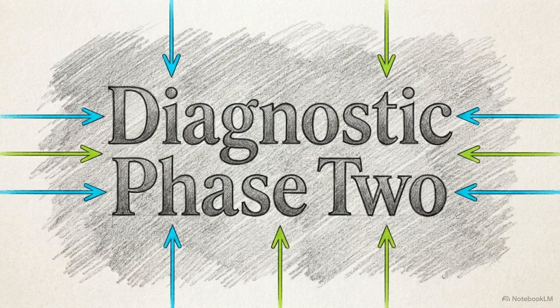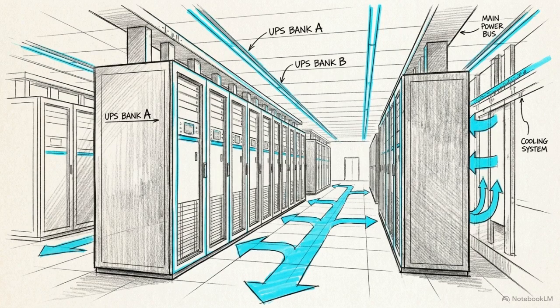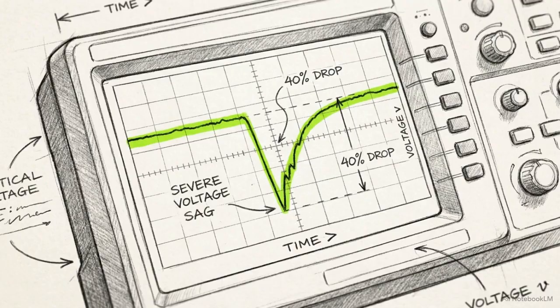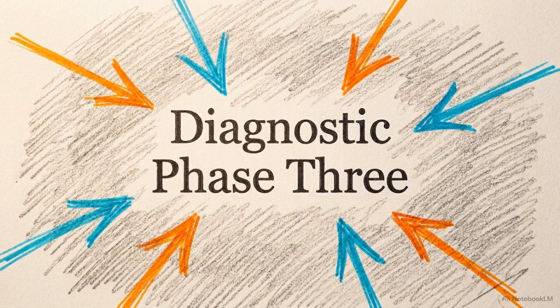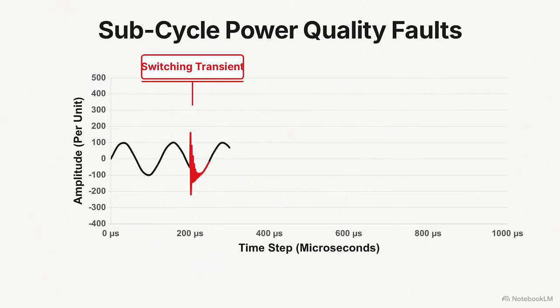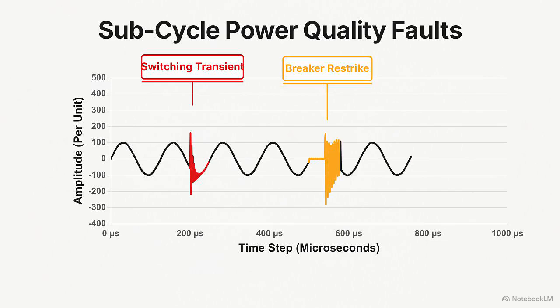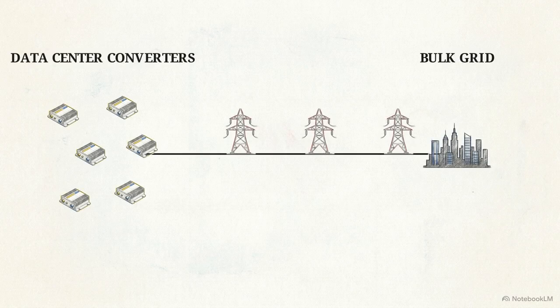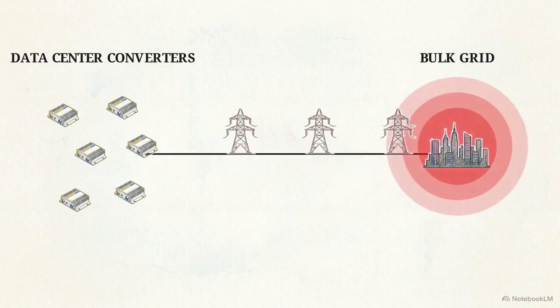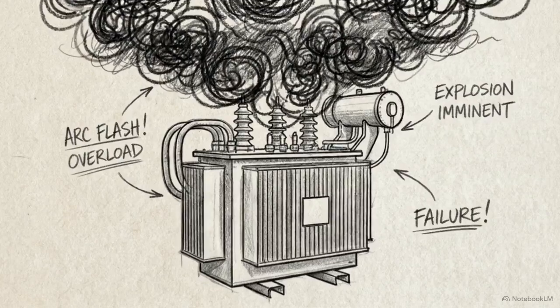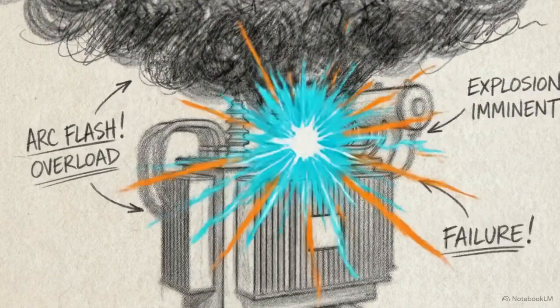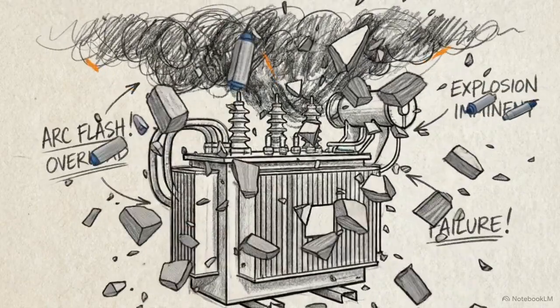The second diagnostic requirement is validating sub-cycle fault ride-through capabilities. The model must capture how the facility's front-end converters and uninterruptible power supply systems respond to severe voltage sags in the span of microseconds. The third requirement is power quality analysis, specifically targeting rapid switching transients, breaker restrikes, and voltage flicker. In weak grid conditions, the control loops of hundreds of individual converters can interact, resulting in hunting behavior that degrades local power quality and propagates through the transmission network. EMT simulation is the only diagnostic tool that reveals these high-speed control interactions before they destroy physical infrastructure.